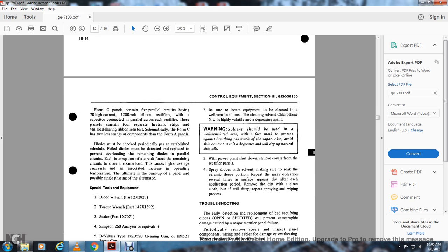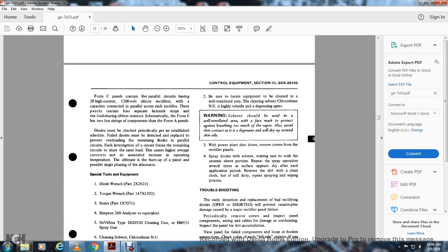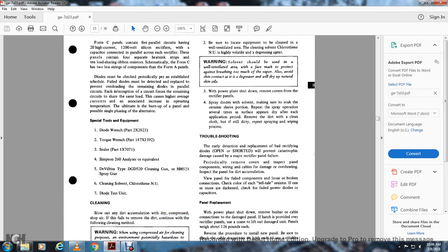Diodes must be checked periodically per the established schedule. Failed diodes must be detected and replaced to prevent overloading the remaining diodes in the parallel circuit. Interruption of the circuit sharing the same load causes high average currents, which increase the operating temperature and ultimately burn up the panel, with possible single phasing of the alternator.